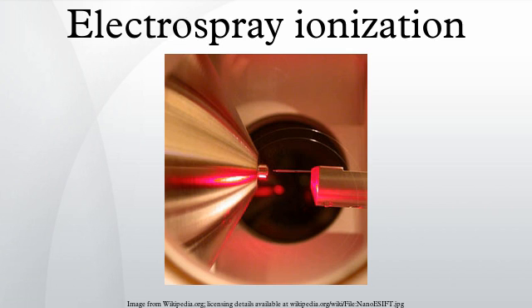These species also act to provide a source of protons to facilitate the ionization process. Large flow electrosprays can benefit from additional nebulization by an inert gas such as nitrogen or carbon dioxide. The aerosol is sampled into the first vacuum stage of a mass spectrometer through a capillary carrying a potential difference of approximately 3000 V, which can be heated to aid further solvent evaporation from the charged droplets.